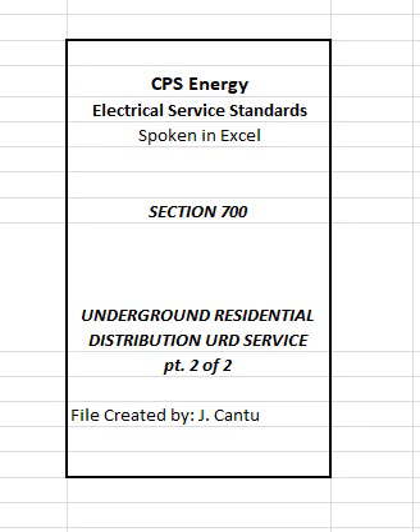705 Service lateral conductors. CPS Energy will furnish, install, and terminate service lateral conductors on the line side of the meter socket. On duplex service installations, CPS Energy will terminate the service lateral conductors in customer-furnished auxiliary wire gutter or in a junction box. Where required, refer to Figure 802. The service lateral size will be based on calculated voltage drop at maximum demand, and maximum service lateral cable pulling tensions. The estimated demand loads and ampacities for meter sockets are outlined in Table 1800-705.